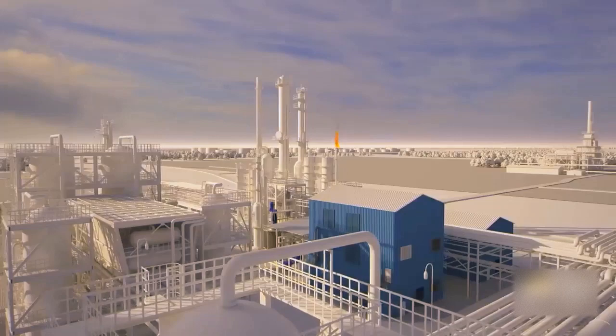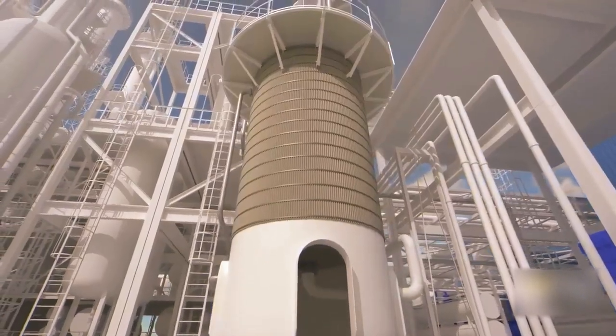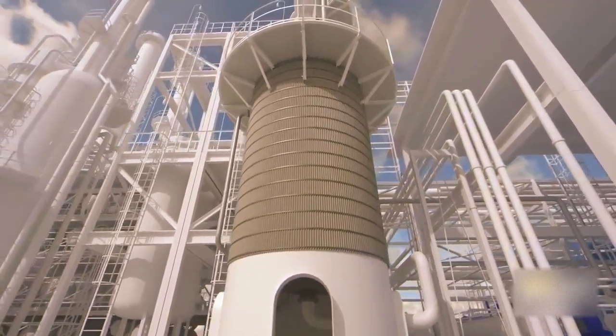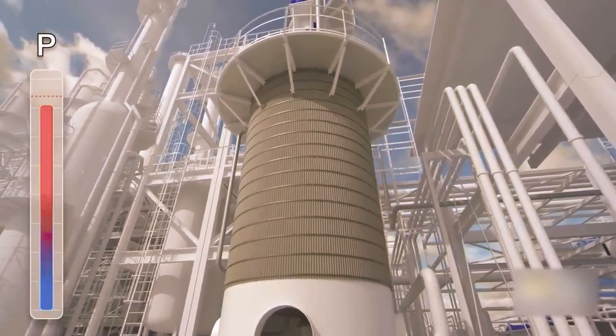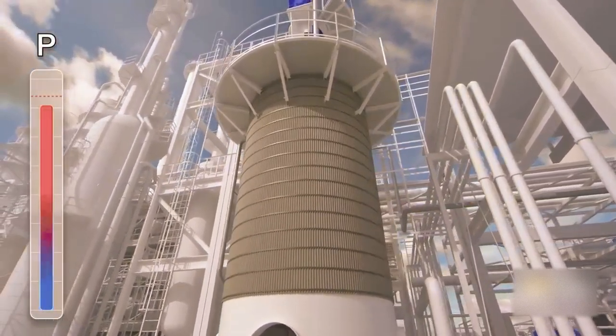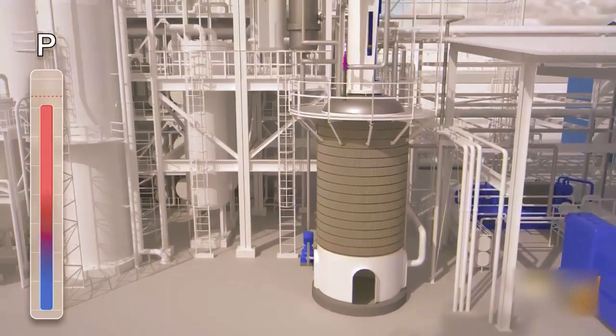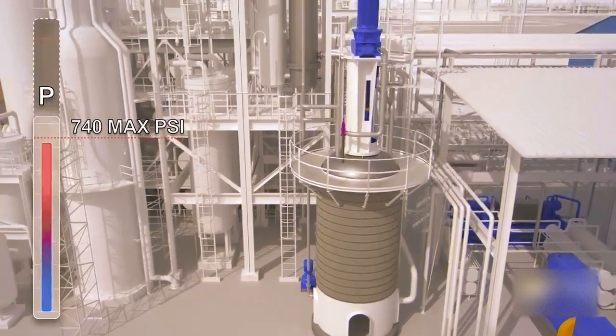Pressure inside the reactor continued to climb. Shortly after 10 a.m., operators initiated the next step in the start-up. At that time, a new board operator took over and noticed the pressure in the reactor was over 700 PSI. But the operator did not recall that this reactor had a maximum design pressure of 740 PSI. He thought it could withstand higher pressure like the others.